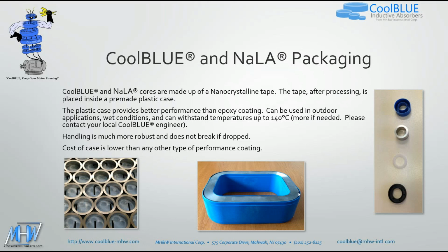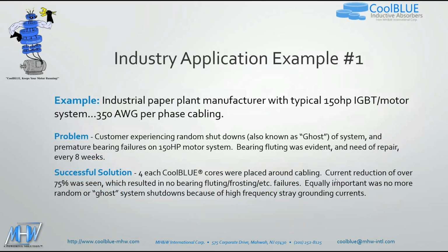One thing to note is that if the plastic case does open up and the core does come out, then it's best that you power the system down and replace the core. This material is very brittle, and it's like a glass-like structure, and you don't want to be messing with it because it can break into small shards. You can get it stuck in your fingers and have an aggravating little sort of splinter in your finger that will drive you nuts. So if one comes apart, carefully remove it and replace it with a new core. Don't try and reuse it, because you don't want it breaking up on you. So let's go through some applications.